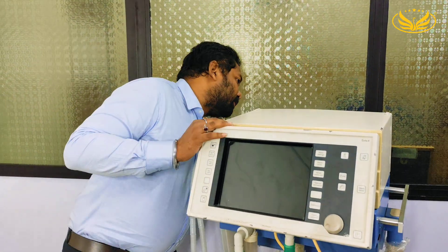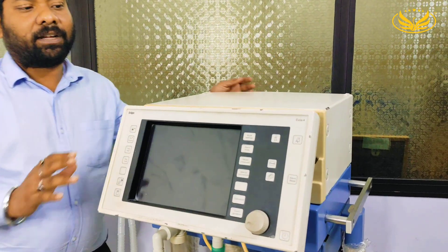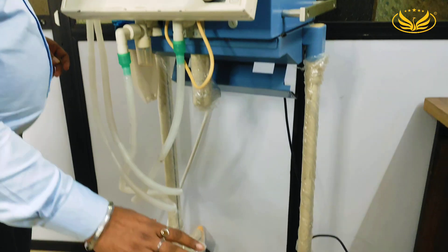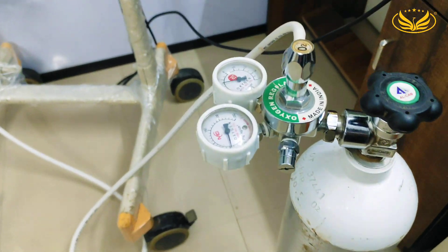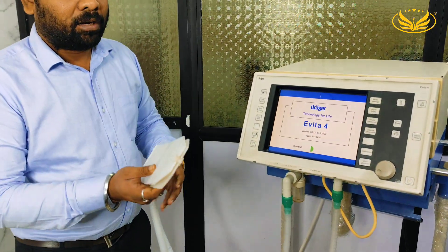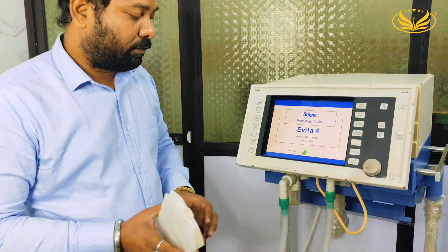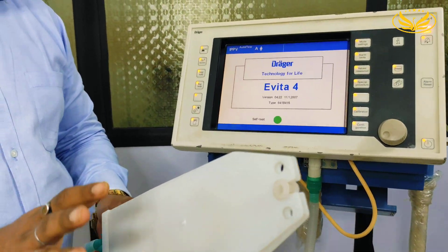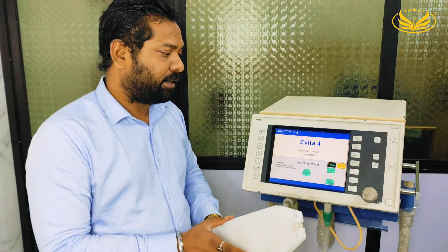Let me start this ventilator, then you will come to know what features we are having in it. Right now we have just connected to oxygen, as an air compressor is not available with us, and we have connected one pediatric circuit along with a test lung. We have used a pediatric circuit, but unfortunately as we are not having a pediatric test lung in stock, we have used an adult test lung for this.